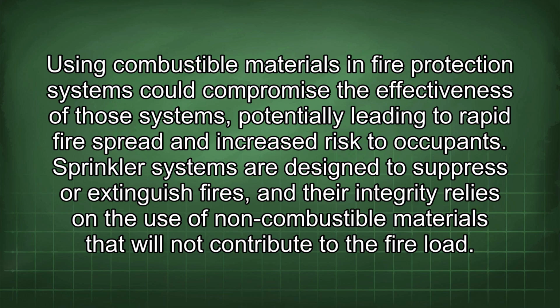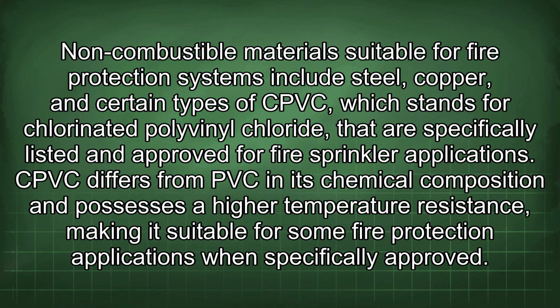Sprinkler systems are designed to suppress or extinguish fires, and their integrity relies on the use of non-combustible materials that will not contribute to the fire load. Non-combustible materials suitable for fire protection systems include steel, copper, and certain types of CPVC, which stands for chlorinated polyvinyl chloride, that are specifically listed and approved for fire sprinkler applications. CPVC differs from PVC in its chemical composition and possesses a high temperature resistance, making it suitable for some fire protection applications when specifically approved.